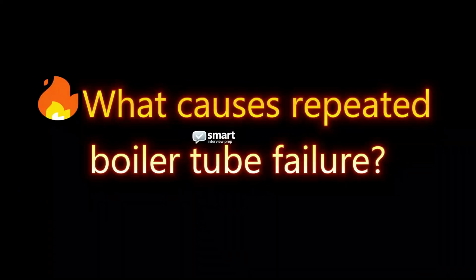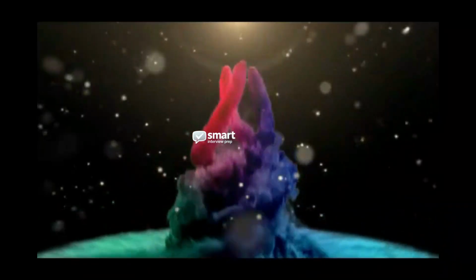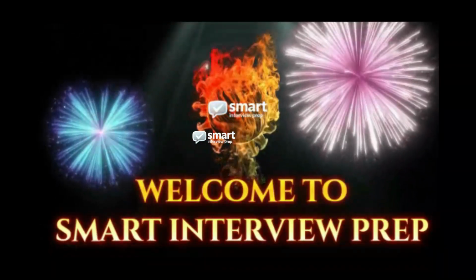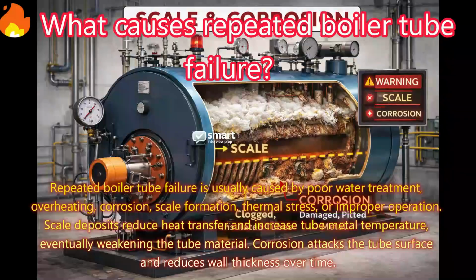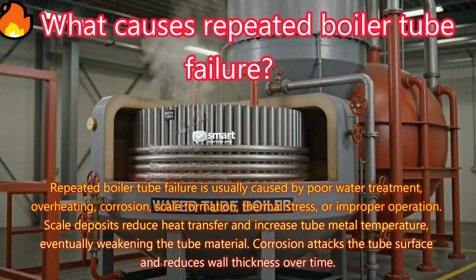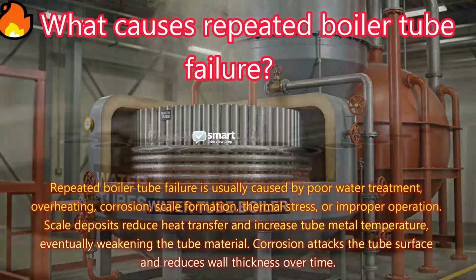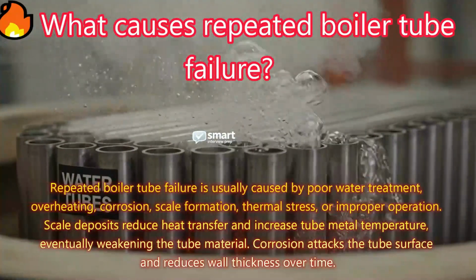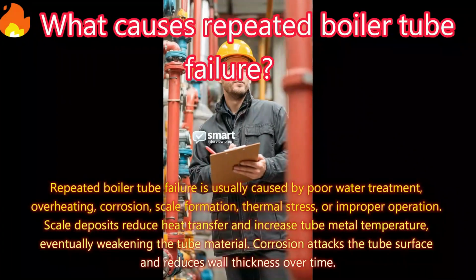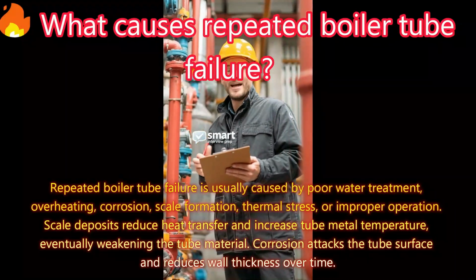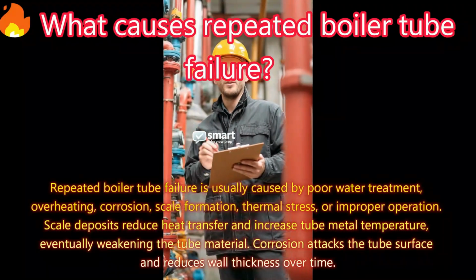What causes repeated boiler tube failure? Answer: repeated boiler tube failure is usually caused by poor water treatment, overheating, corrosion, scale formation, thermal stress, or improper operation. Scale deposits reduce heat transfer and increase tube metal temperature, eventually weakening the tube material.